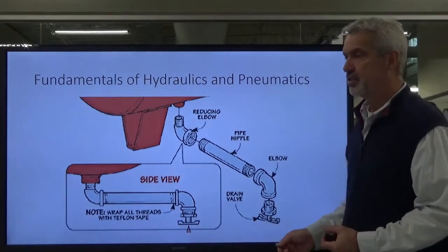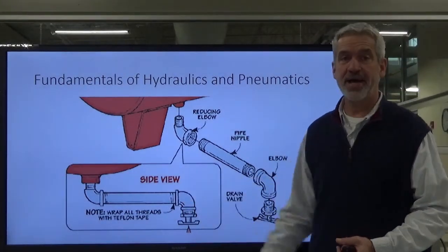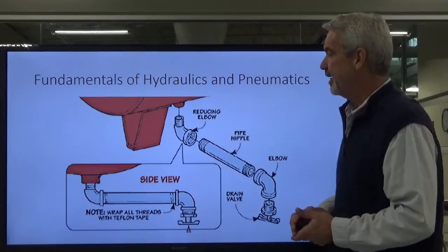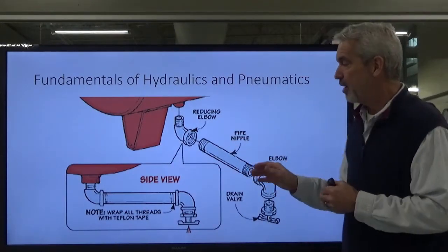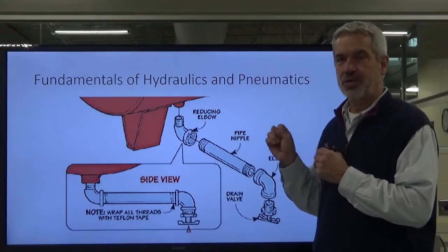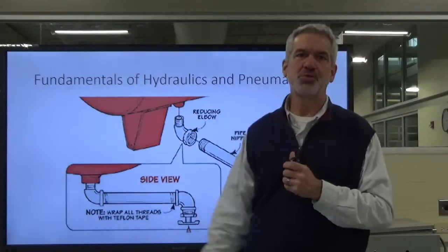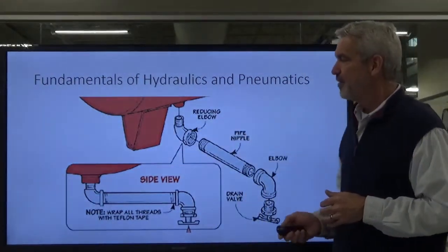We live here in Kentucky and we've got a lot of humidity. Your compressor pulls that humid air in there and it compresses it and stores it in the tank. That includes the humid air, the water. What will happen is the water will settle out in the bottom of the tank and there's typically a drain valve that you'll want to drain that off. That's part of your maintenance for a pneumatic reservoir. You have to drain that off. I've worked in some places where gallons and gallons of water will come out of an air compressor tank or a reservoir.